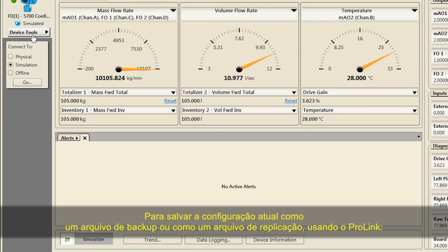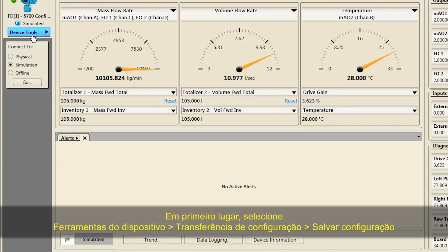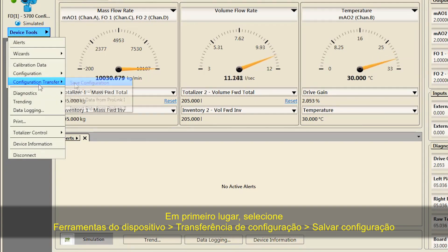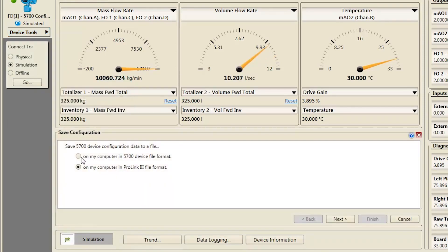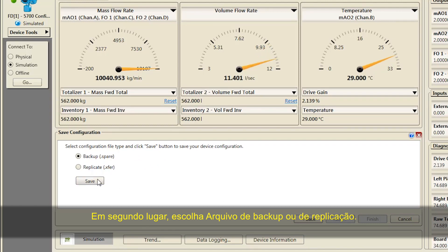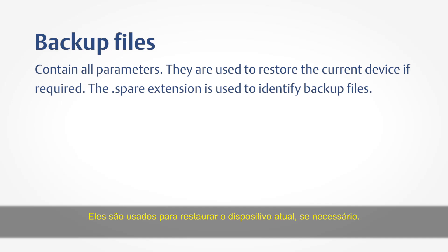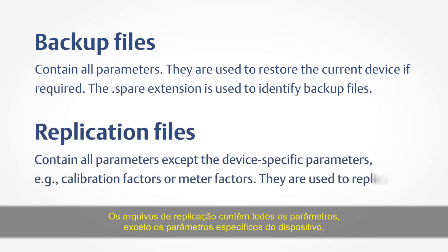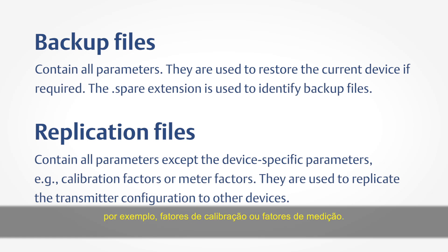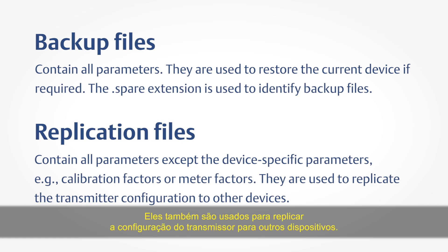To save the current configuration as either a backup file or a replication file using ProLink: first, select Device Tools, Configuration Transfer, Save Configuration. Second, choose Backup or Replicate File. Backup files contain all parameters and are used to restore the current device if required; the .spare extension is used to identify backup files. Replication files contain all parameters except device-specific parameters, such as calibration factors or meter factors, and are used to replicate the transmitter configuration to other devices.